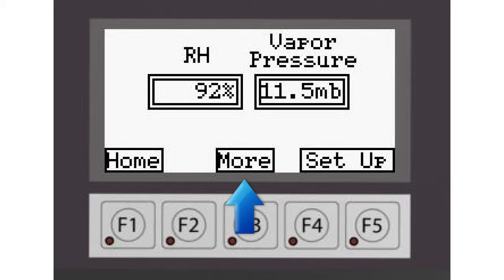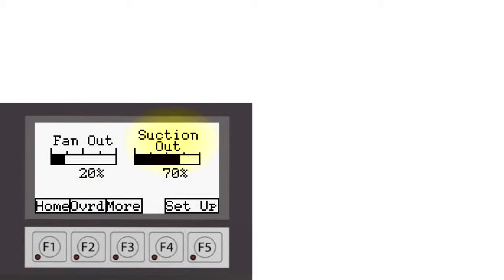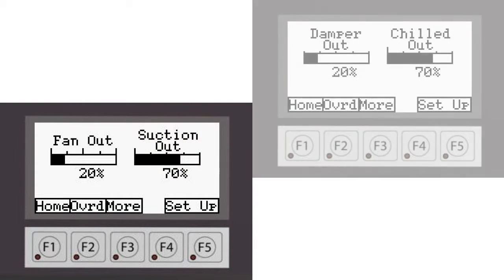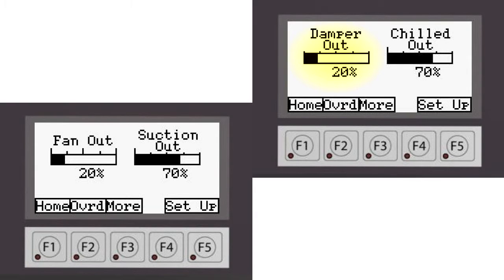Pressing the more button takes you to the next screen. On this screen, you can see the speed that your fan should be running at and the position of the refrigerant suction valve. Some controls instead of having a fan output will have a damper output and instead of a suction output might have a chilled water output. But the effect is the same.